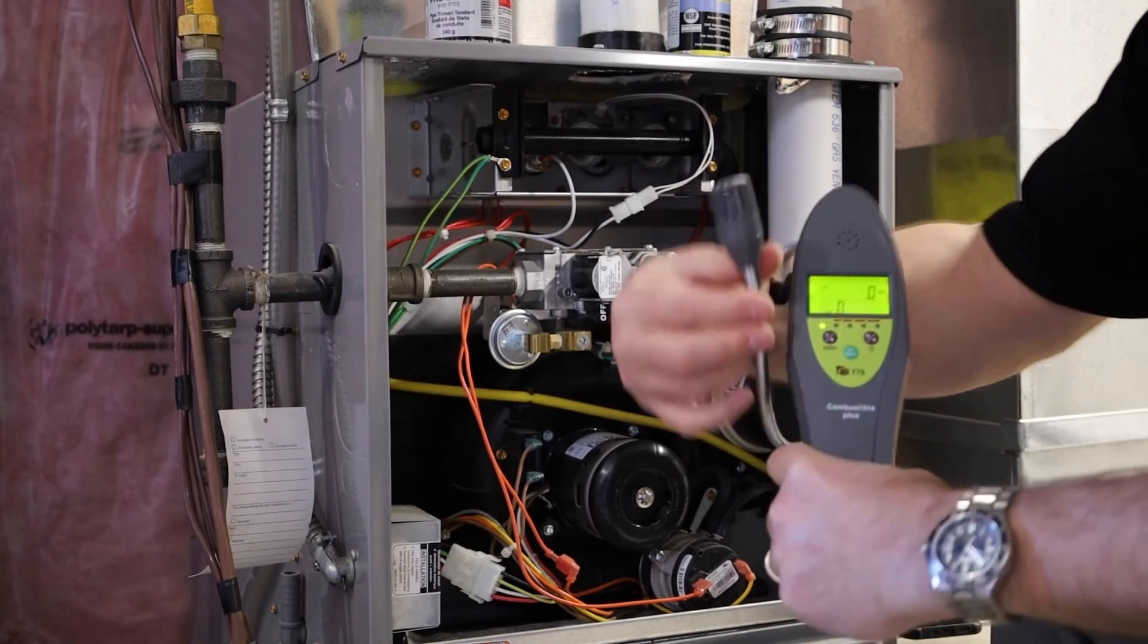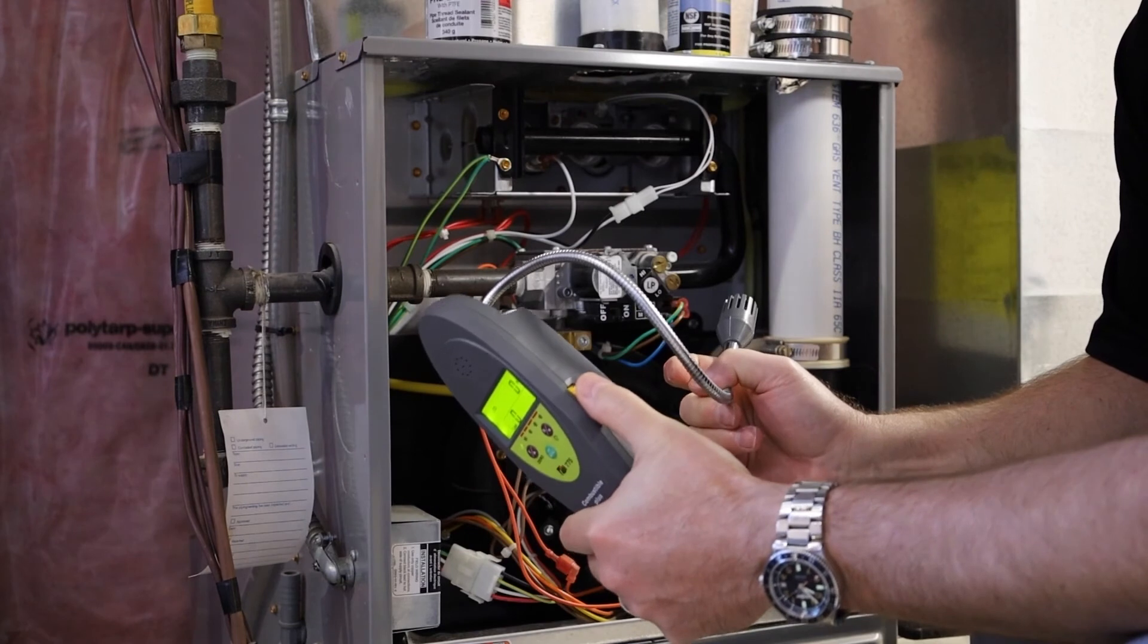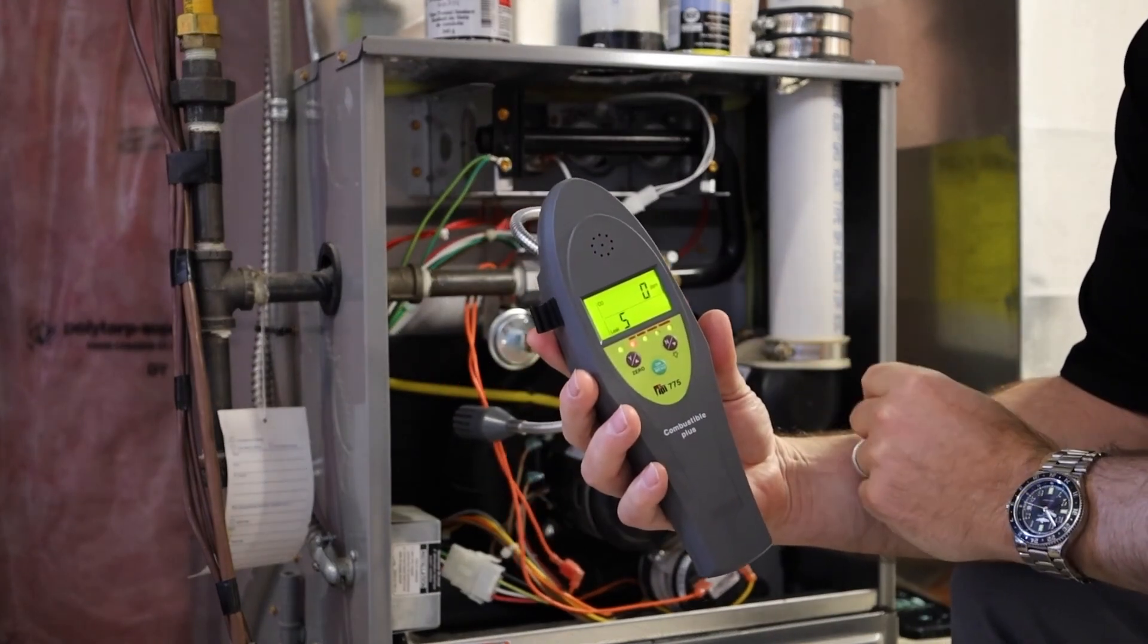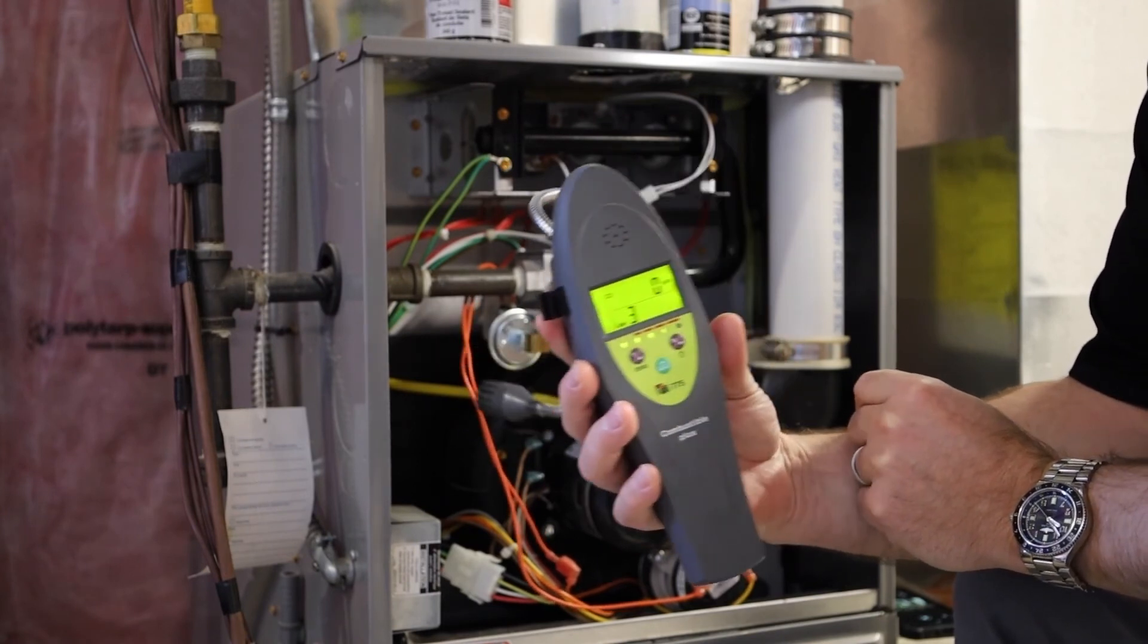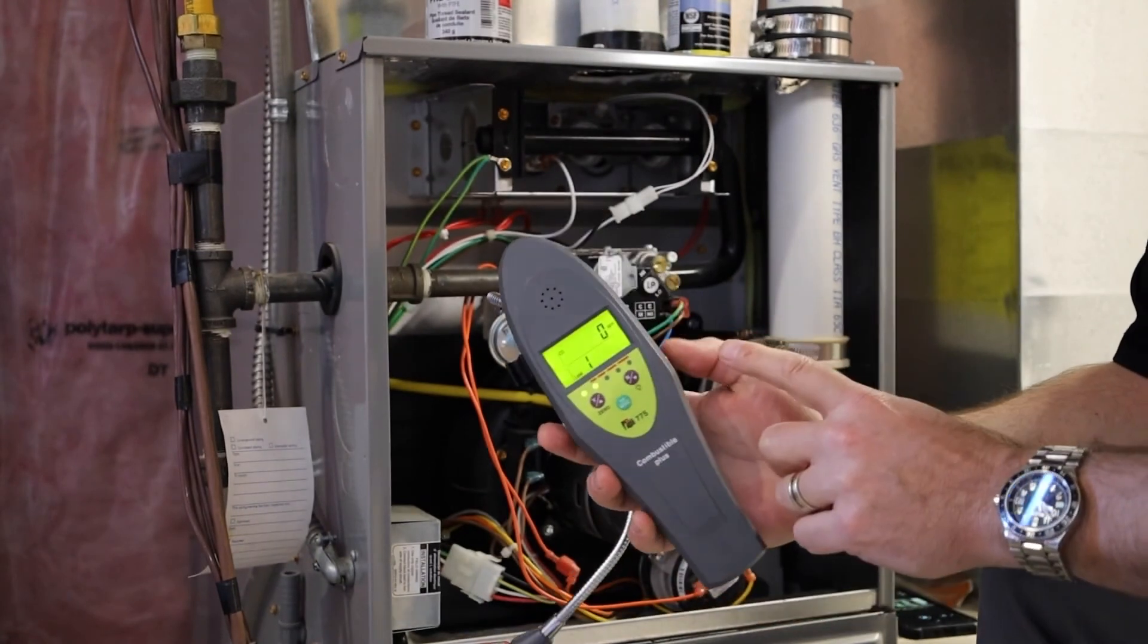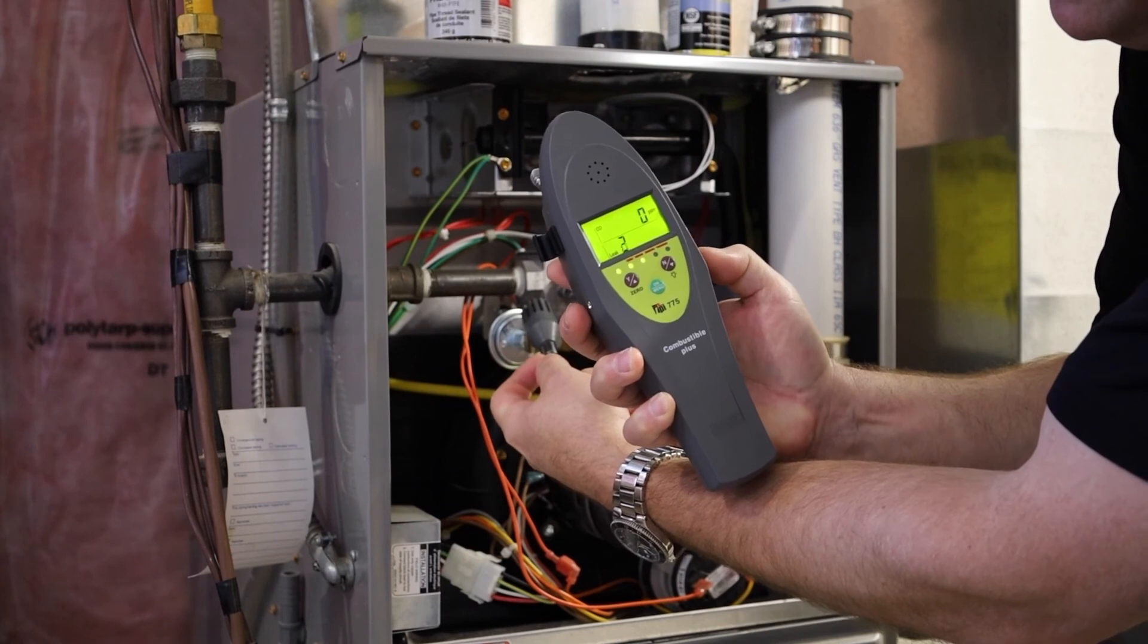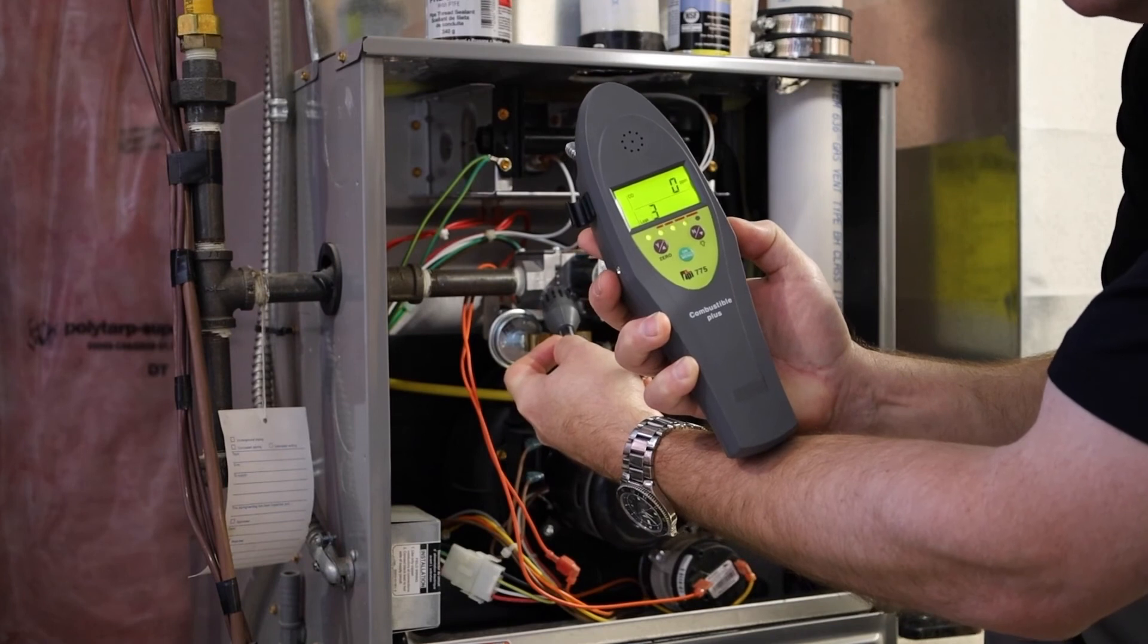Gooseneck. I'm going to go over to my leak. I've got my thumb wheel on the side. So I'm going to just go over to my leak here. And of course, there it is, going off. Oh, that's a big leak. So I'm at five. So that indicates that leak is between 2,000 and 2,500 parts per million. And if you want to look around for the leak there, you got it there. And then you have the tune button on the side. So you can actually tune it out. And when it goes to higher ppm, it's going to start beeping again.